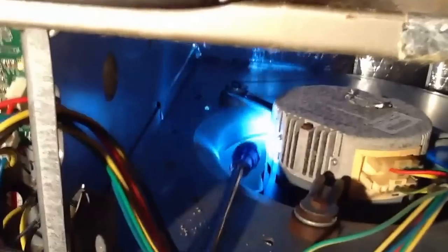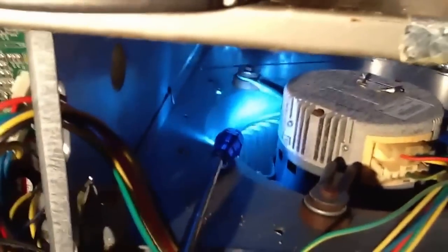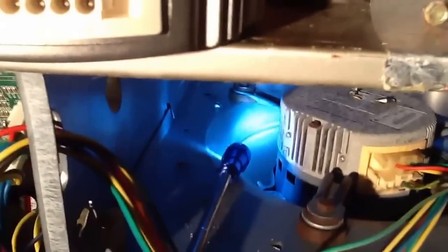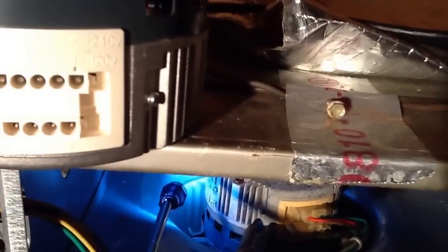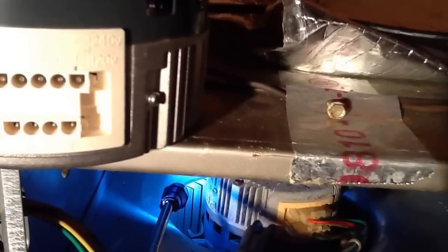The module is burned up inside, so this motor has to be replaced. If you're getting the situation where you see a motor trying to spin, it means the module is bad. And I see it kicked out.